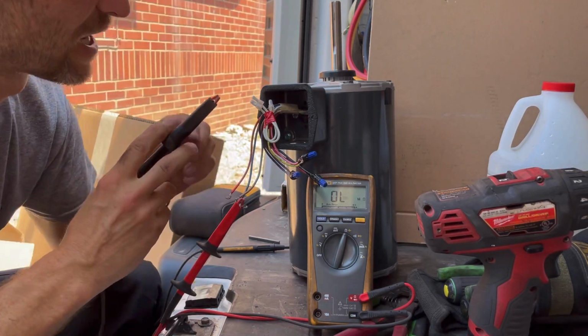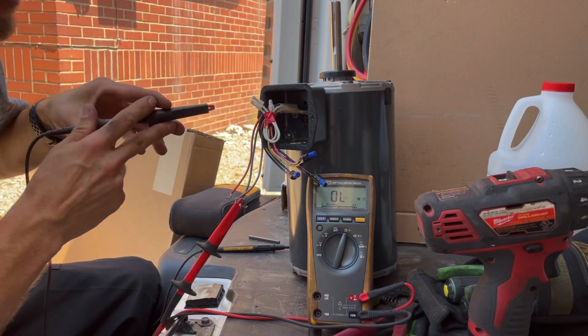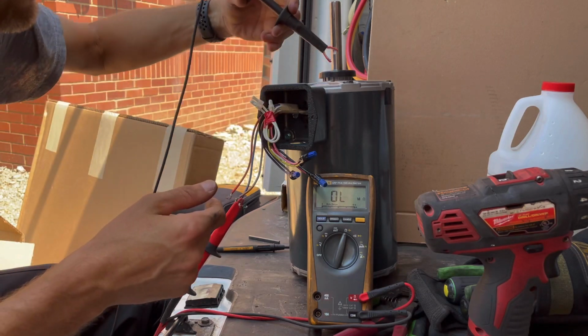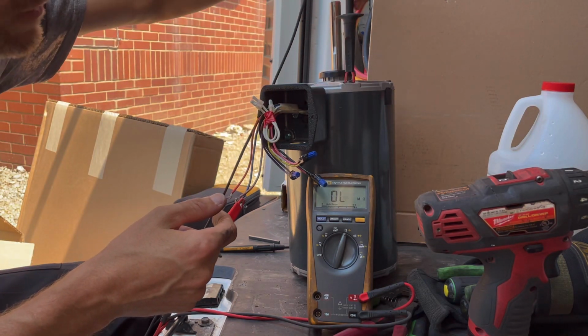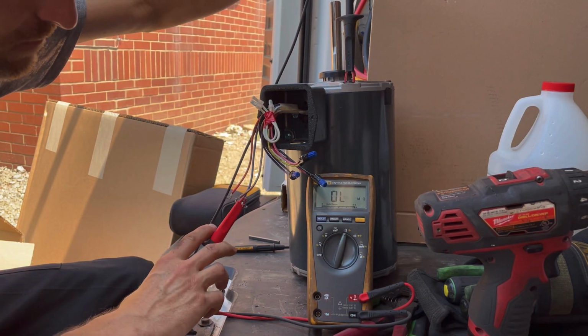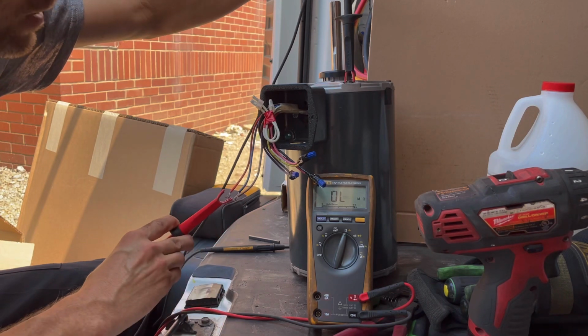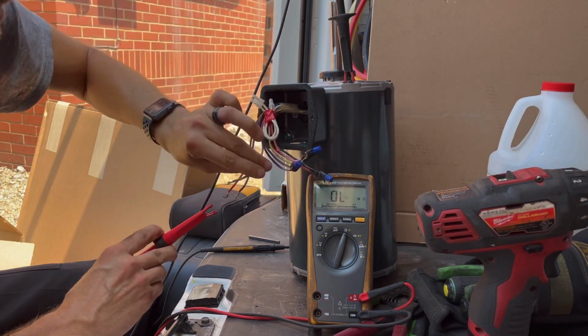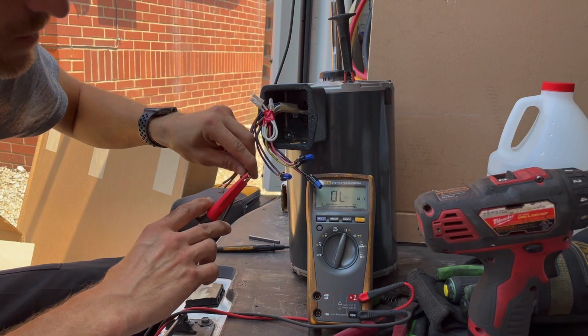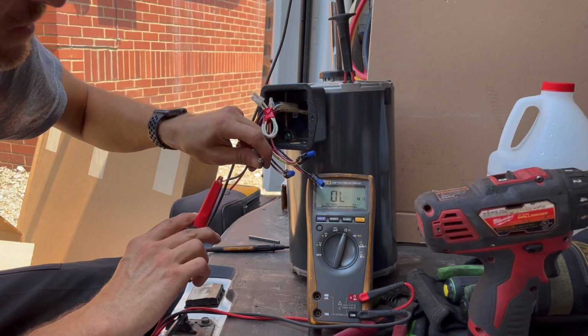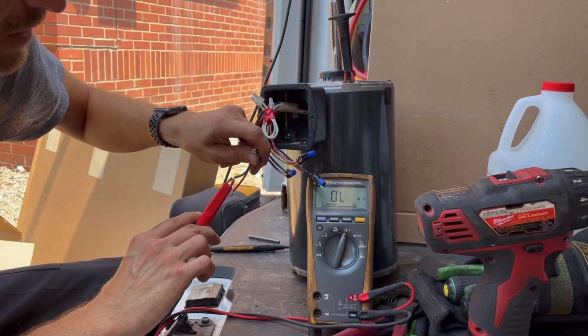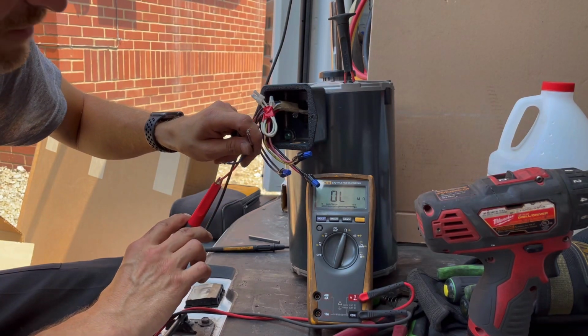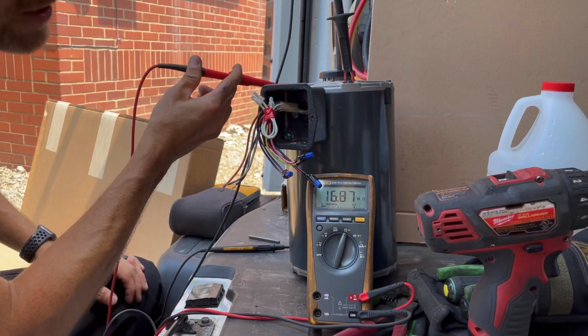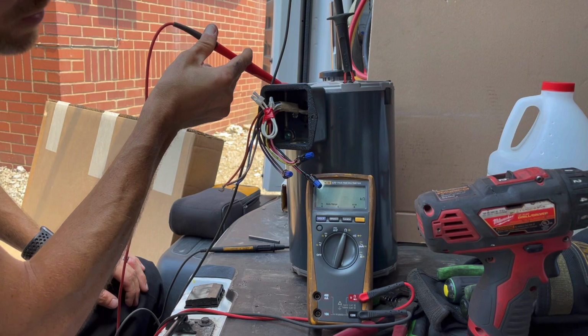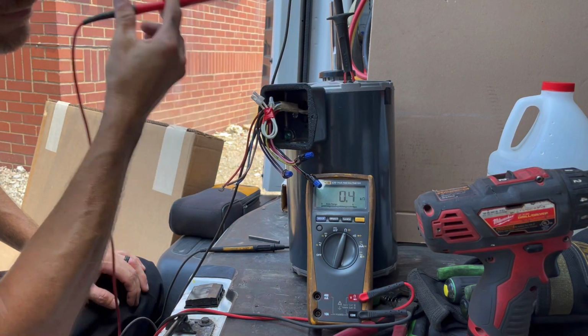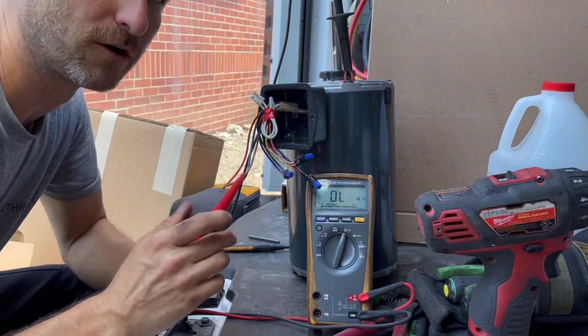Now we check it to ground as well. So I'm gonna grab just right onto, you can grab the ground lug or you can grab onto the case or the shaft. Okay, not touching ground. Try to separate these, I'm sorry. Not touching ground. Not grounded. Not grounded. Okay, now if it were touching ground, we would see something like this where it's reading that. But end result, you want to see OL.